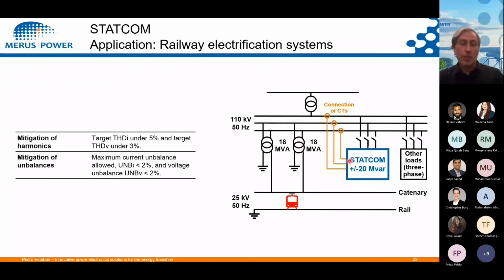In this case, the whole output, or the current, needs to be provided in real time, so we can take care of harmonics and imbalance at the moment the train is going through this area of the railway. Harmonics have very standard values to mitigate, and customers typically ask for imbalance in the current and imbalance in the voltage to be less than 2%. So there will not be any issues created for the other loads that we have in the system.